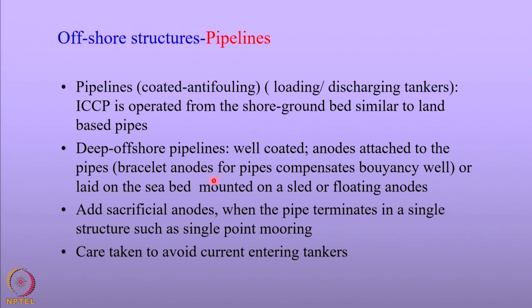The anodes are attached to the pipes as bracelet anodes, which also reduces buoyancy by adding weight to the pipeline, or the pipeline can be laid on the seabed mounted on a sledge or with floating anodes. Sacrificial anodes are added wherever the pipeline terminates in a single structure such as single point moorings.